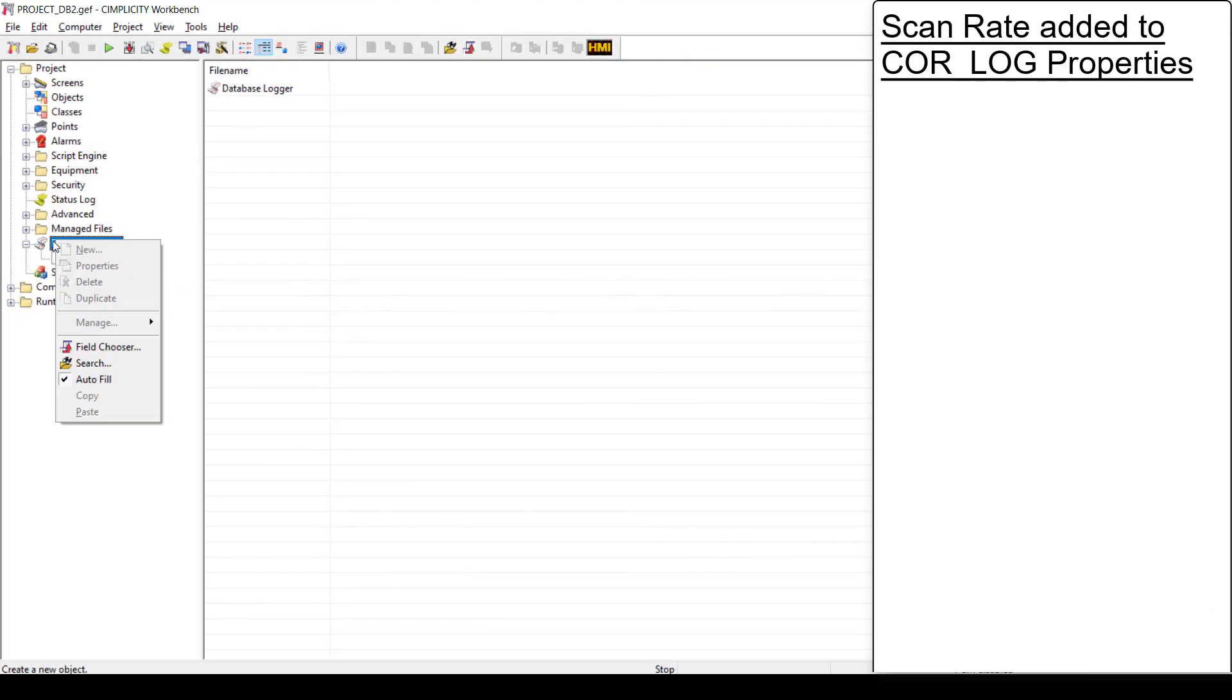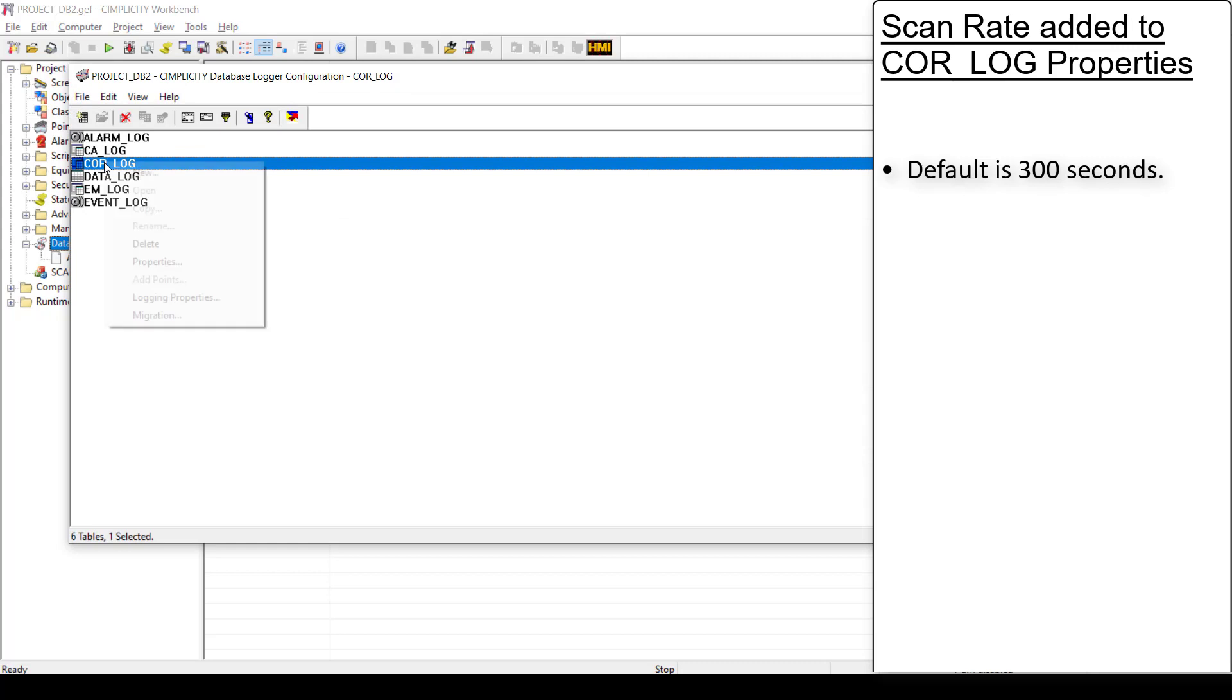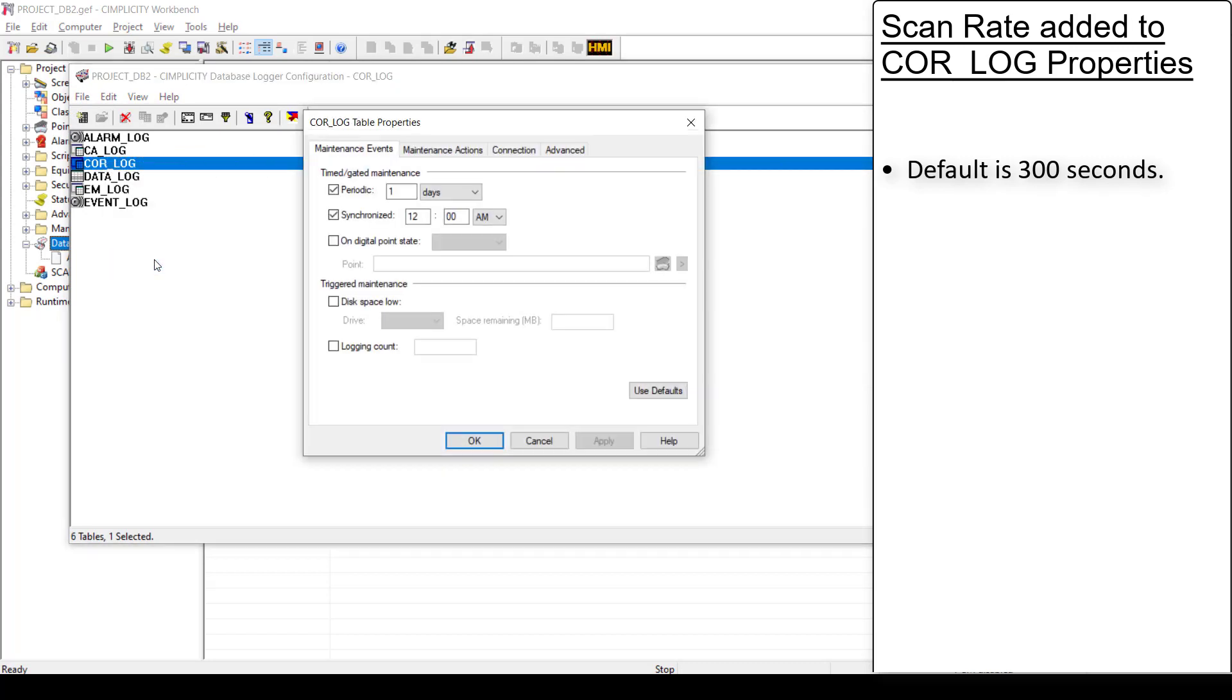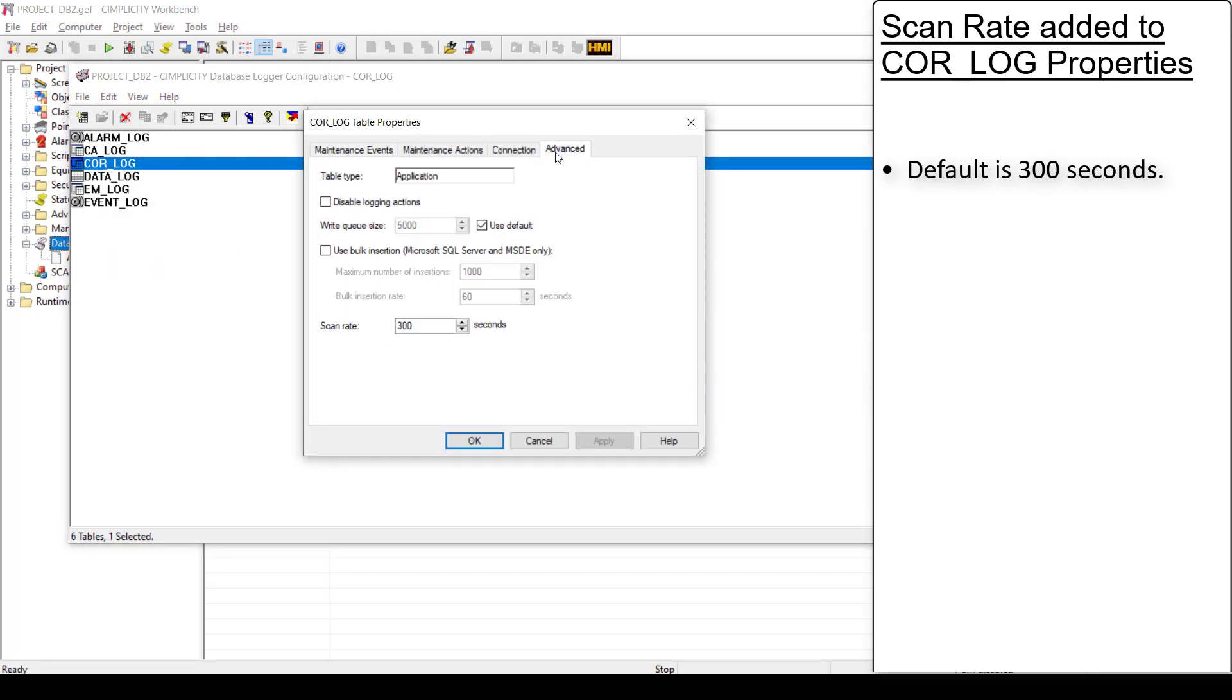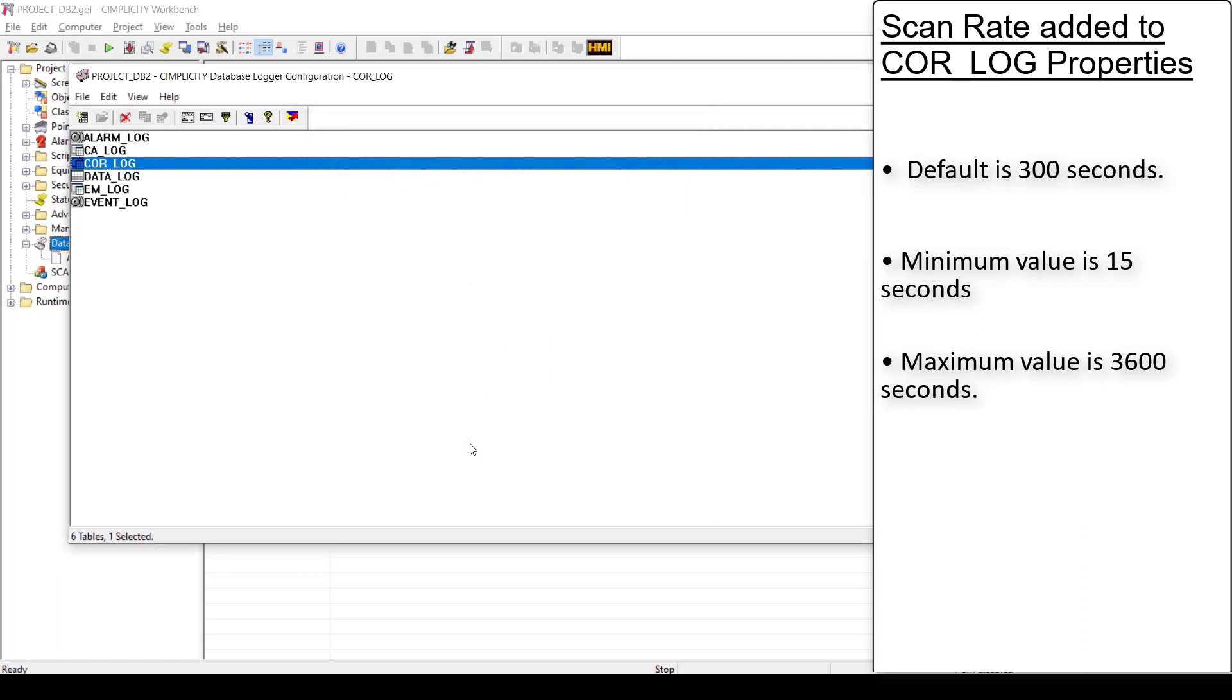In COR_LOG Properties, when you open the Advanced tab, you can see that a new field called Scan Rate is added. It is the rate at which you want to scan the status log for the records. The default value is 300 seconds. Minimum allowed is 15 seconds and maximum is 3600 seconds.